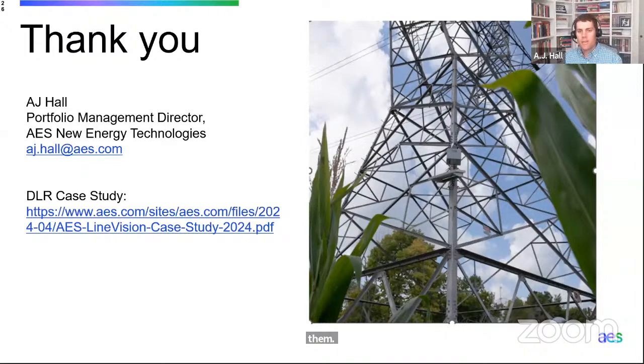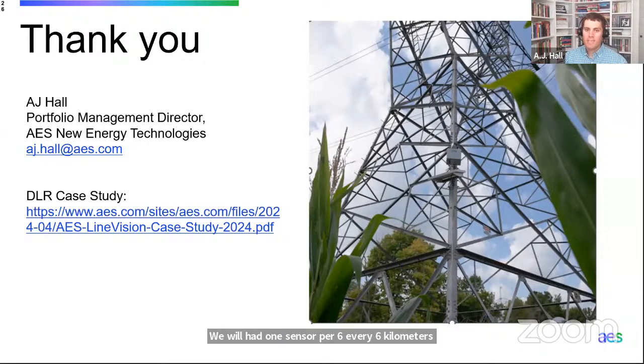It kind of varies based on voltage. As you see here, this is a 345 kV line. We really had one sensor approximately every 6 kilometers, but it can sometimes be less than that if there's a line heading change. Wind direction can change based on when the line takes a turn, and since wind is the most important factor in calculating DLR, we have to put a sensor to capture the effect of wind for that line heading change.